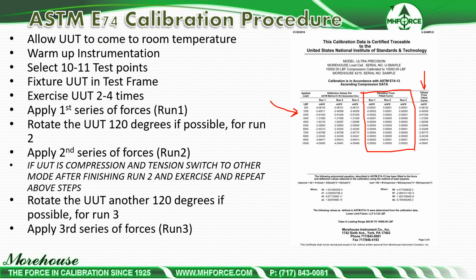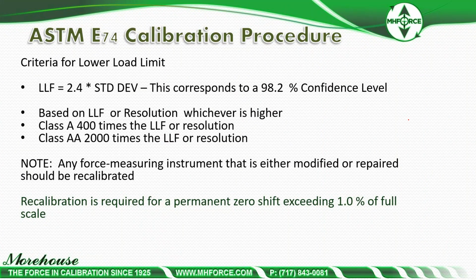And then from these values, we're going to take the deviations from each of the observed points, which is basically the values from the fitted curve minus what we actually observed during calibration. So we're going to take all of that, sum the squares, and then multiply it by 2.4, which corresponds to roughly 98.2% confidence. And we're going to base everything on the lower limit factor or resolution.